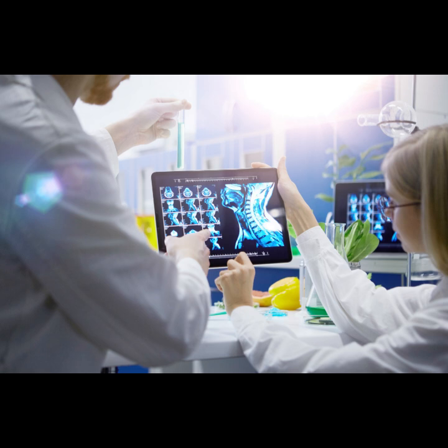Now, beyond just noise and blur, the way we sample K-space can introduce very specific image artifacts too, right? Like if we try to speed things up by reducing the field of view, the FOV. Yes, particularly if you reduce the FOV in the phase encoding direction, which is tempting because it means fewer phase encoding steps and thus a faster scan. But if the part of the body you're imaging is actually larger than that reduced FOV, bits outside get chopped off. They don't just get chopped off. They wrap around and get superimposed on the other side of the image.